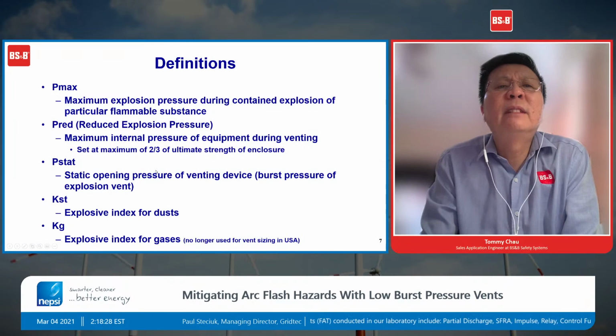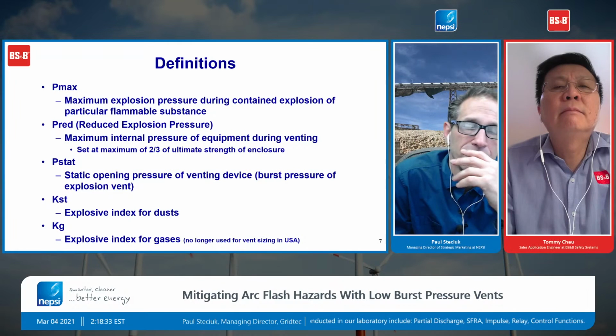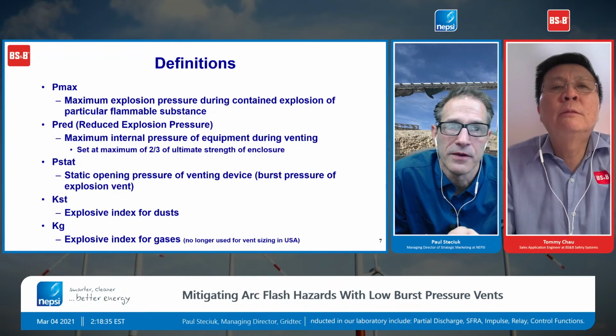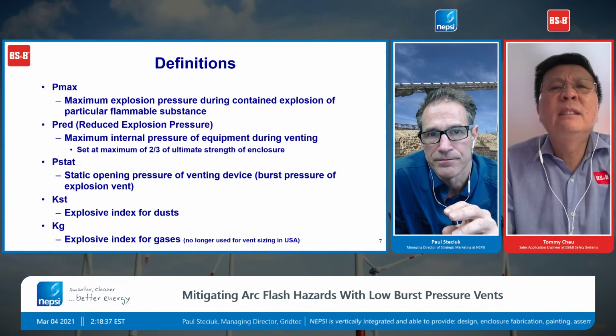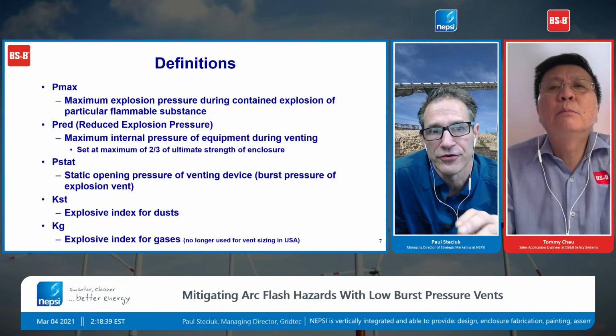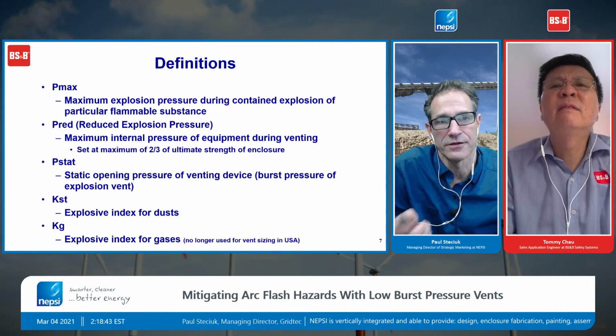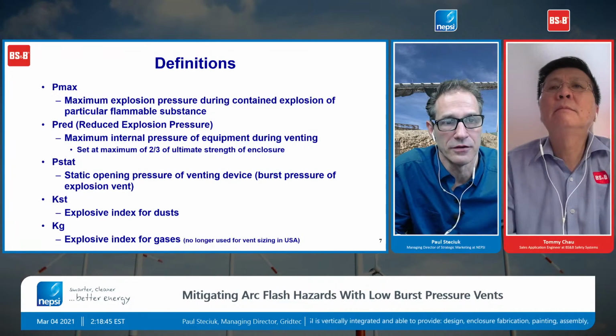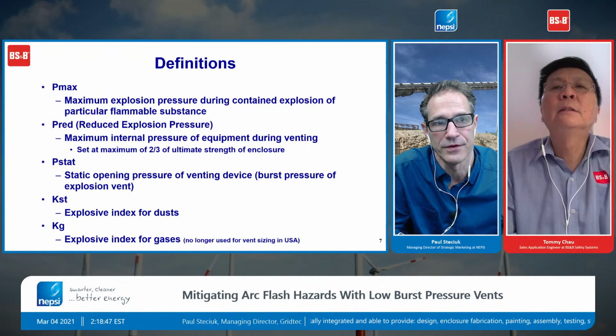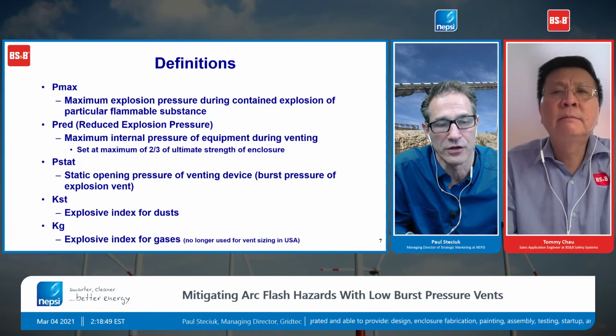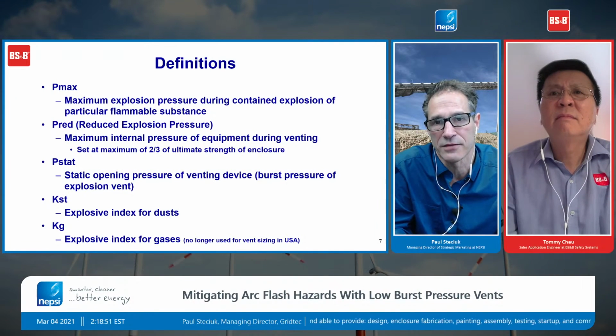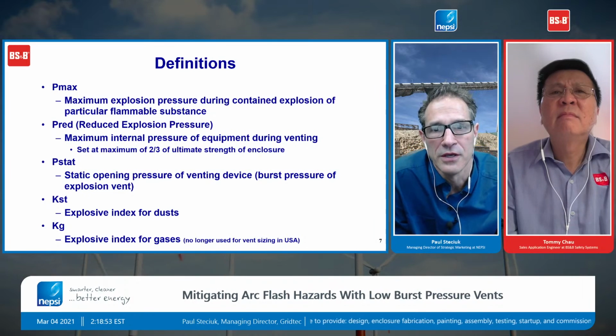Hey, Tommy, maybe I can comment here a little bit too. So Pmax is the maximum explosion pressure during a contained explosion of the particular flammable substance. Basically, this is how much pressure you're going to get inside the enclosure for the explosion. Correct. For our case, it would be the arc flash event causes some type of maximum pressure inside that enclosure.